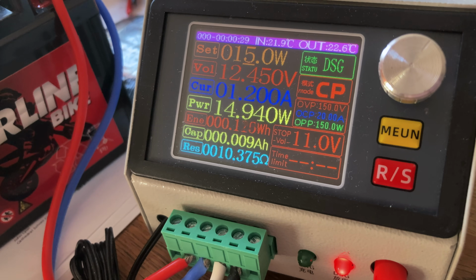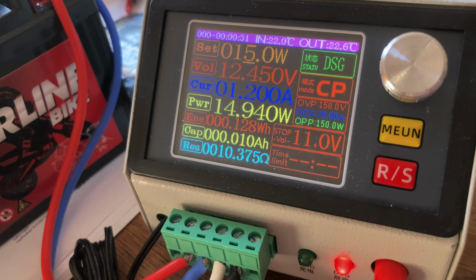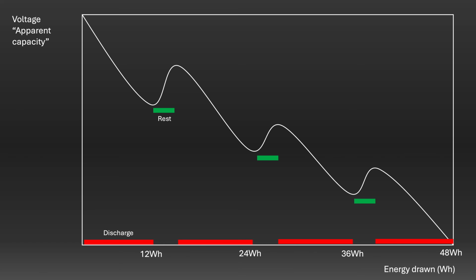I'm not running a continual measurement like those software-driven machines can, but instead this is my system. We stop at increments along the way, recording the under-load voltage at the start and finish of each segment. We then rest and allow the voltage to recover, record that and move on.